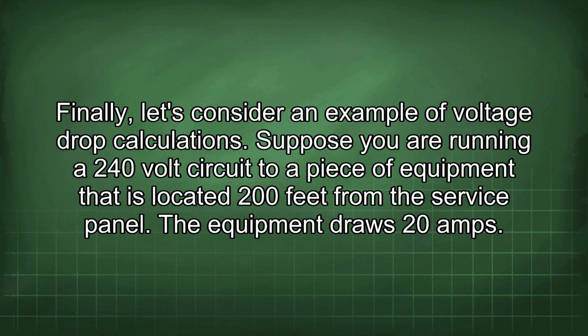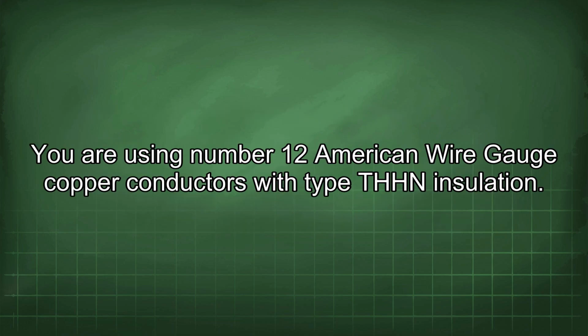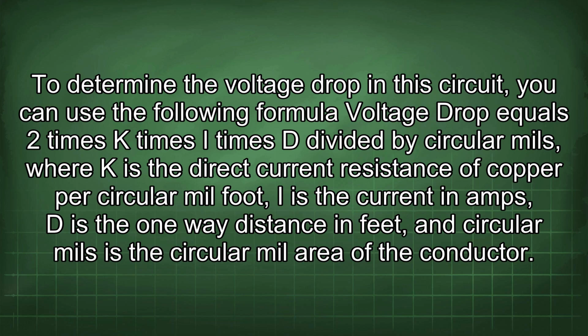Finally, let's consider an example of voltage drop calculations. Suppose you are running a 240 volt circuit to a piece of equipment that is located 200 feet from the service panel. The equipment draws 20 amps. You are using number 12 American wire gauge copper conductors with type THHN insulation. To determine the voltage drop in this circuit, you can use the following formula: voltage drop equals 2 times K times I times D divided by circular mils, where K is the direct current resistance of copper per circular mil foot, I is the current in amps, D is the one-way distance in feet, and circular mils is the circular mil area of the conductor.